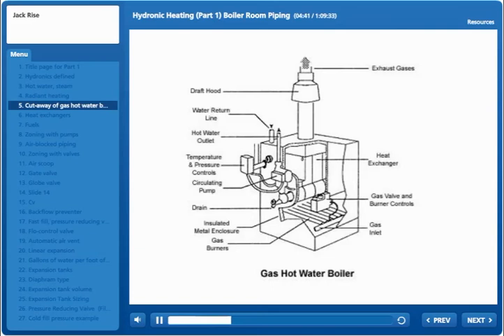All right, you can see the drain. The drain would let the water out of the heat exchangers, the cast iron heat exchangers, and I'm going to show you a much better picture of that in a few slides from now. But again, the drain would just drain the sections, the cast iron sections. You see the circulating pump, the water circulating pump. The temperature and pressure controls, that would be some sort of an aquastat, A-Q-U-A, like the Latin word for water, aqua. You see the hot water outlet and inlet. They actually have them reversed there, but that's okay. You see the draft hood, and then, of course, the exhaust gases going to the flue pipe, which eventually ends up in some sort of vertical chimney.